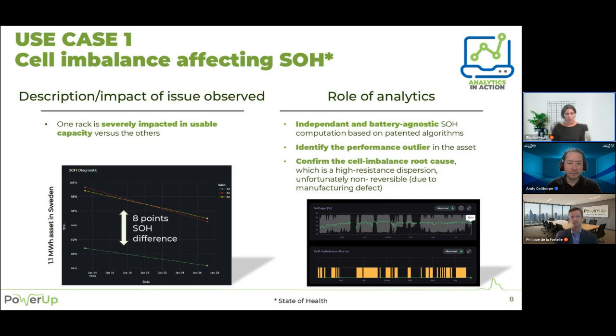Not only was the PowerUp tool able to detect this difference in performance, it could also explain why it happened. In this case, the result comes from a cell issue during the manufacturing phase. The important thing to keep in mind is that if we had used the tool directly at commissioning, we would have detected the fault immediately and could have replaced the battery from the start, letting the system run at the full capacity the owner really wanted, which was not the case here.